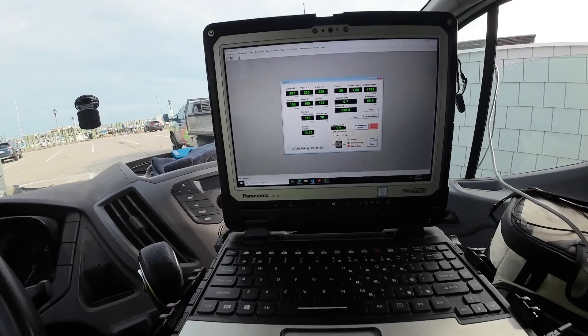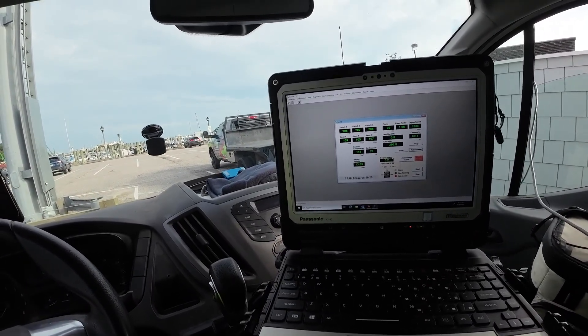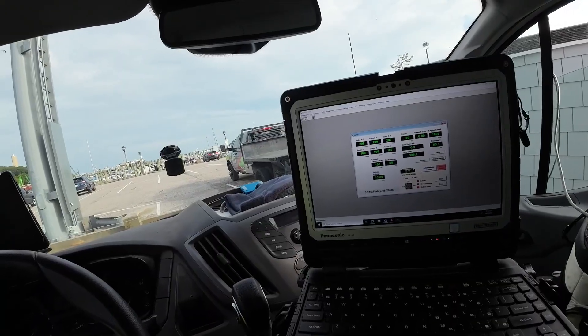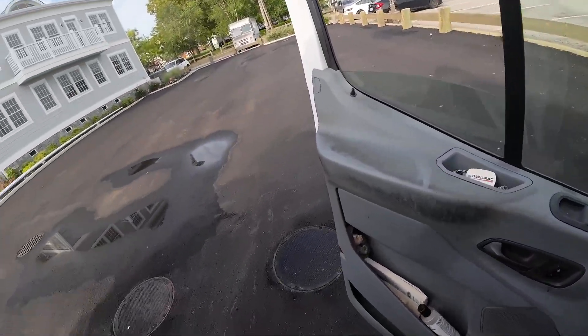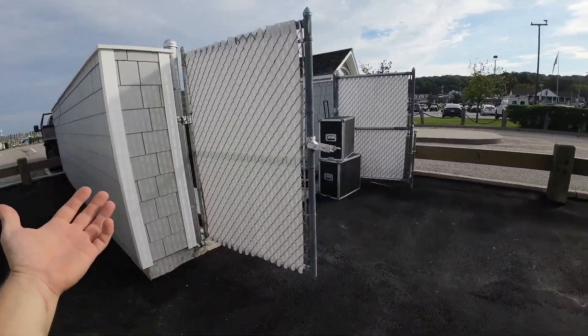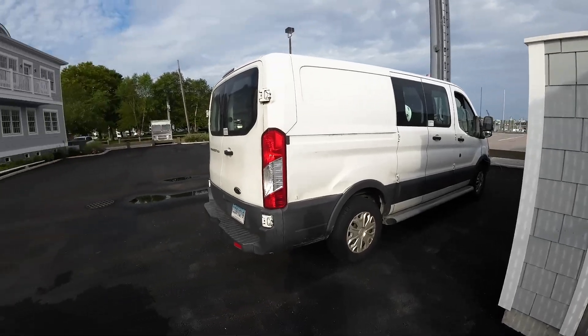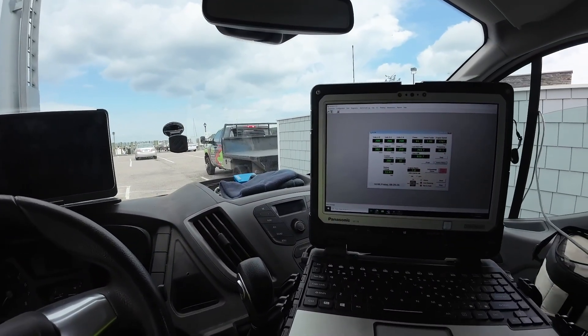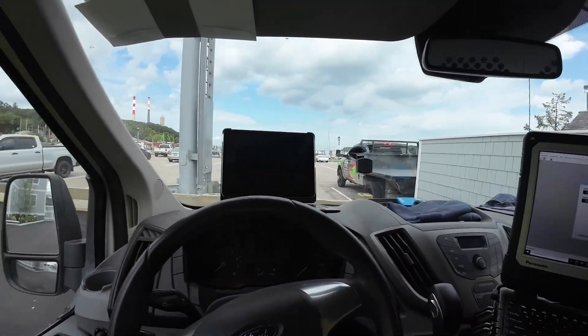So we'll see how low this one gets. This is a cool part — we can monitor the generator from here and make runs back and forth, make sure it's all good. For the most part we can have it all set up right here, which is great because I can have my iPad and fill out the load bank report as it's happening, right in the comfort of our van. Let me get this thing running at full load, get started on some paperwork, and call into dispatch. It's a big test so I don't know how much is going to be filmed — it's a 6-hour test.